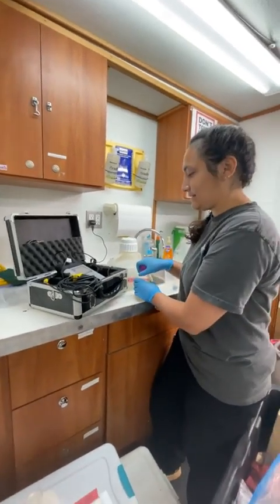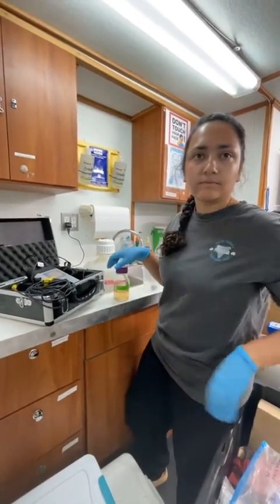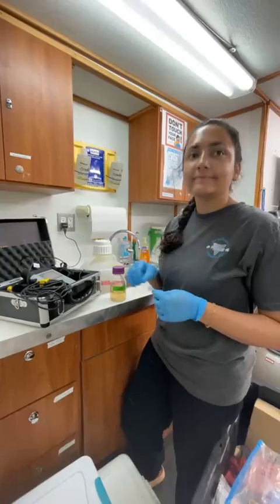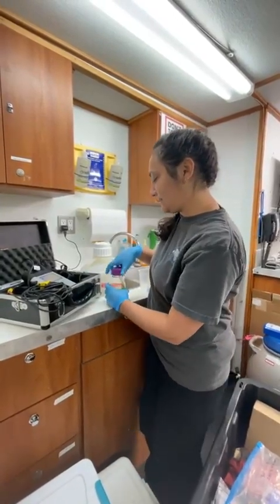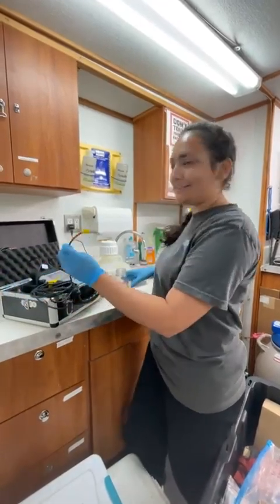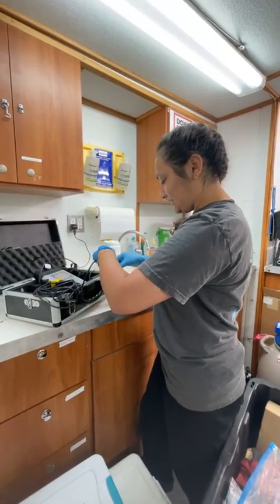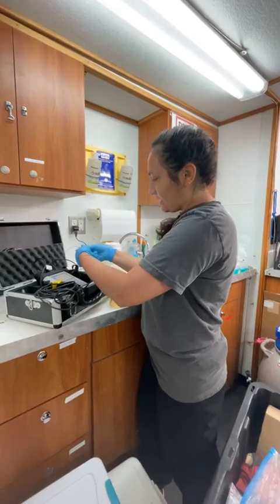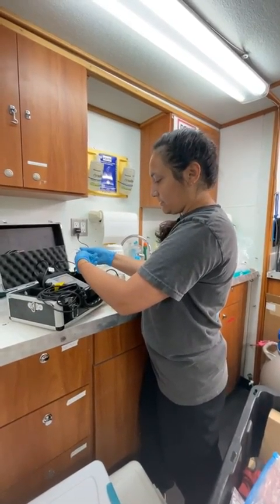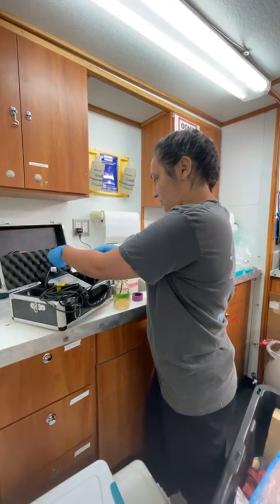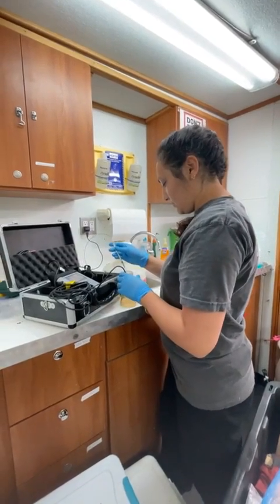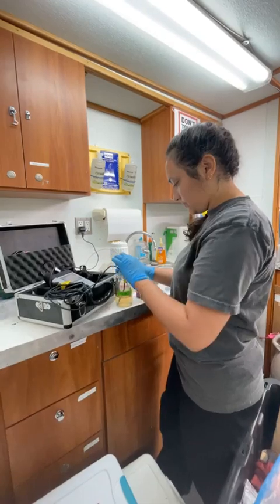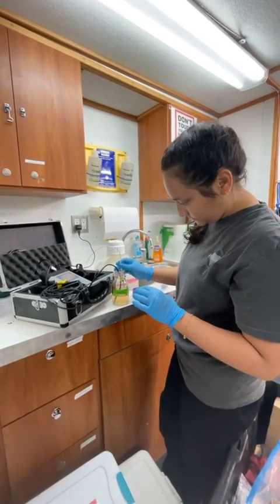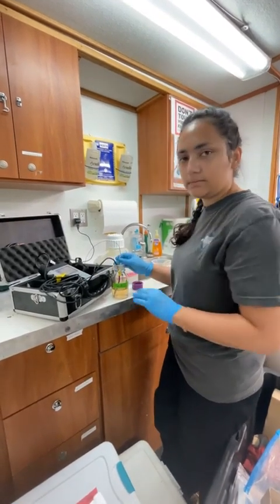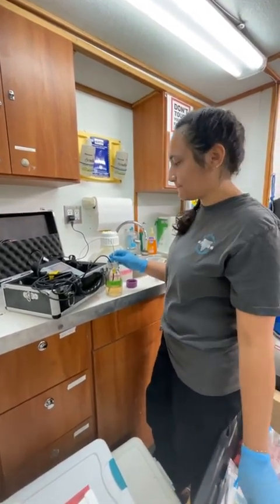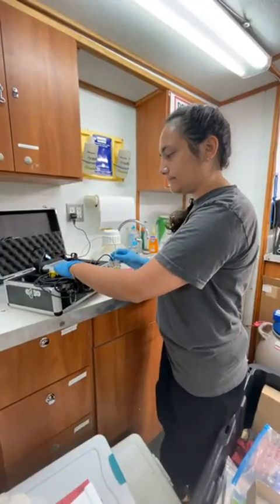So your low calibration sample was formulated to take all of the oxygen out of solution, so that you theoretically have zero oxygen. Or close to zero. So I just put the temperature probe in, and then I very gently push out the little fiber optic cable. And it's important to have the temperature reading along with the oxygen reading, because the temperature will affect the liquid's or the sediment's potential for holding oxygen.